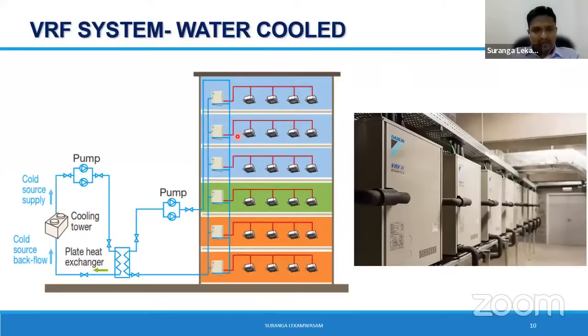Basically, you have water-cooled condensers, because the condenser is cooled by water, similar to water-cooled packages. Then you need to have your condenser water circuit similar to normal water-cooled systems. They are really efficient because, you know, when you compare air-cooled versus water-cooled systems, water-cooled are much better in efficiency, because you can recall your fundamental pH diagram. When it is water-cooled, your condenser operating temperature is lower than air-cooled, and therefore your compressor lift is less, so your COP increases.